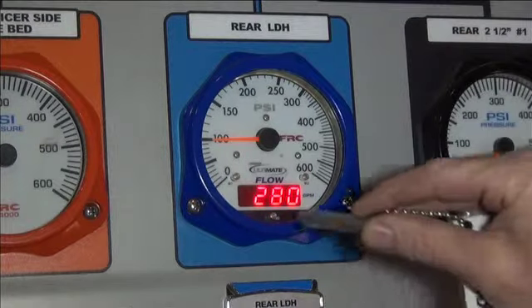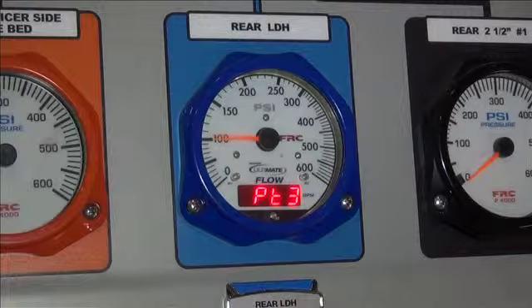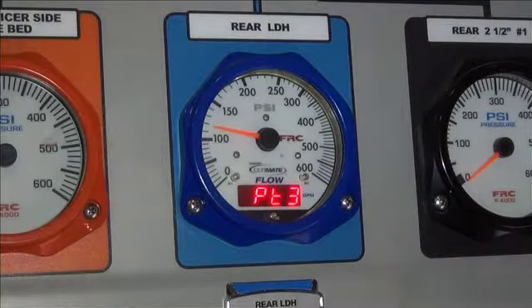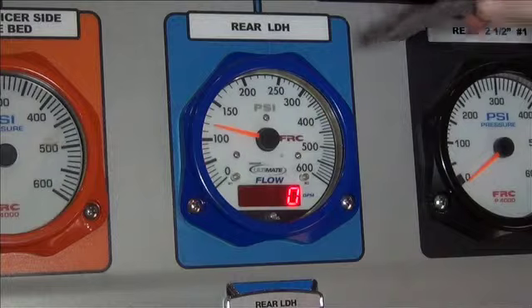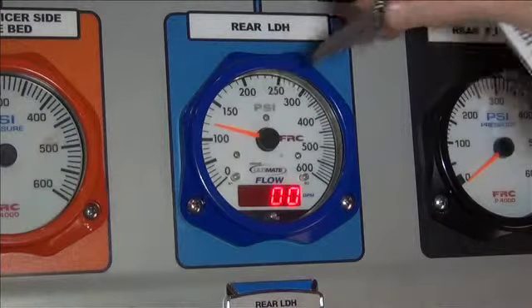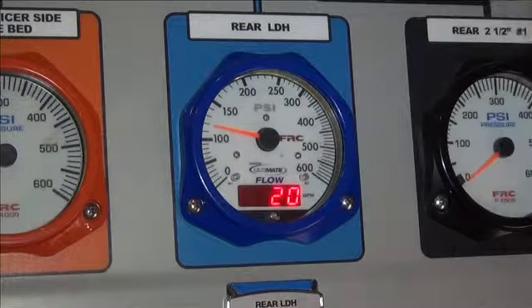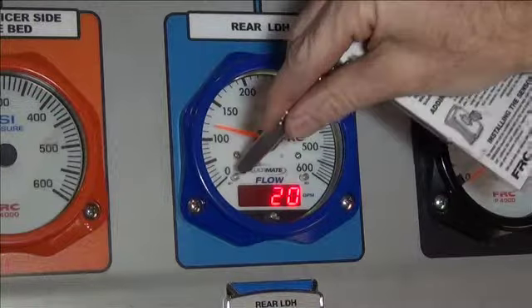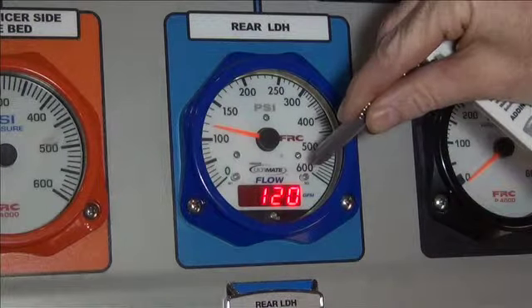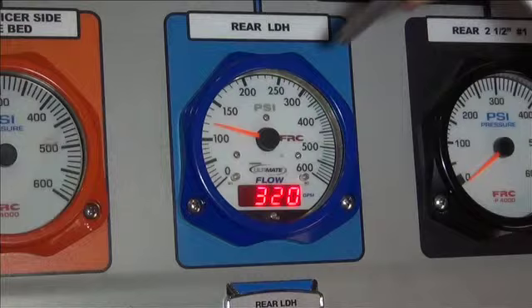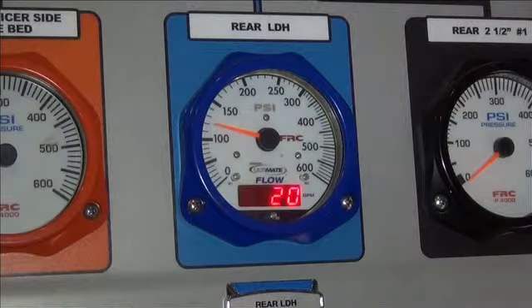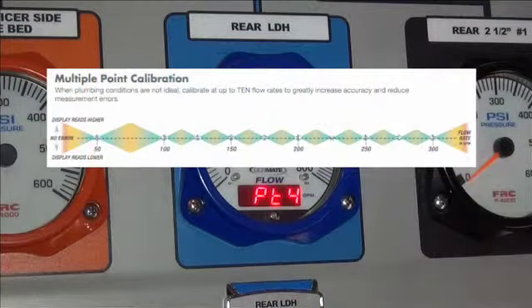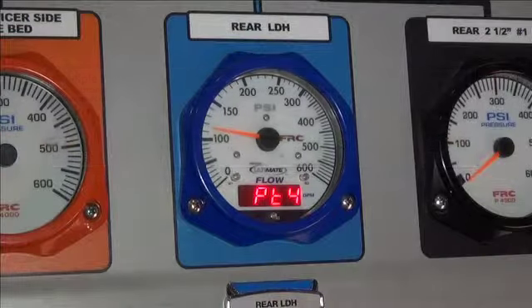Continuing, touch the magnet to the M3 sensor briefly. The display now shows PT3, the third calibration point. We will repeat the procedure as before by first touching the M1 sensor to select the digit to change, touching the M2 sensor to change the digit, and finally touching the M3 sensor to move on to the next calibration point. You can repeat these steps for up to 10 different calibration points.